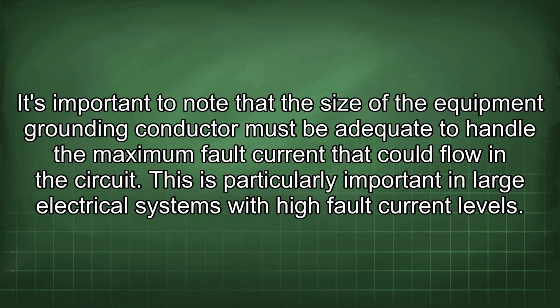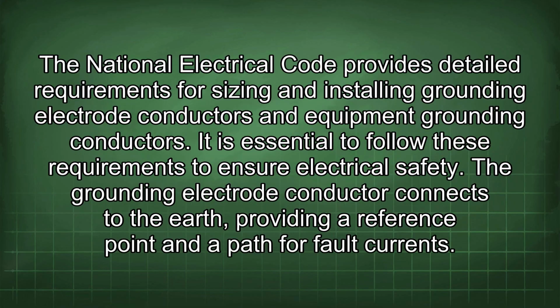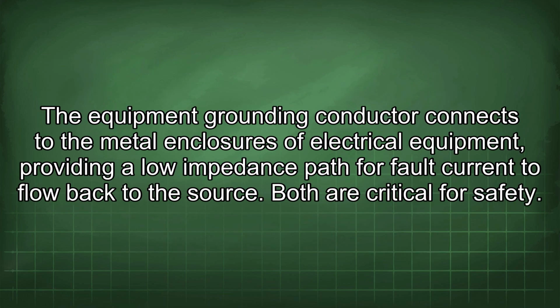It's important to note that the size of the equipment grounding conductor must be adequate to handle the maximum fault current that could flow in the circuit. This is particularly important in large electrical systems with high fault current levels. The National Electrical Code provides detailed requirements for sizing and installing grounding electrode conductors and equipment grounding conductors. It is essential to follow these requirements to ensure electrical safety. The grounding electrode conductor connects to the earth, providing a reference point and a path for fault currents. The equipment grounding conductor connects to the metal enclosures of electrical equipment, providing a lower impedance path for fault current to flow back to the source. Both are critical for safety.